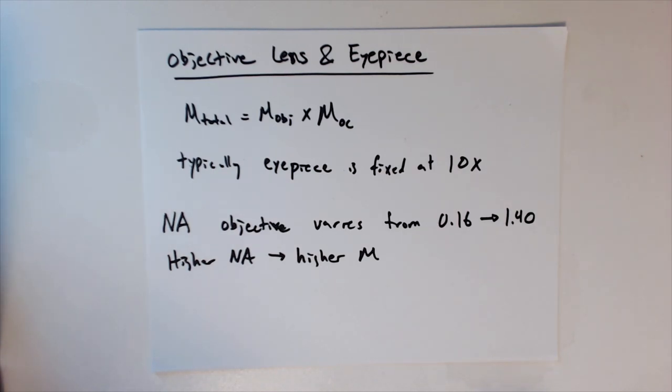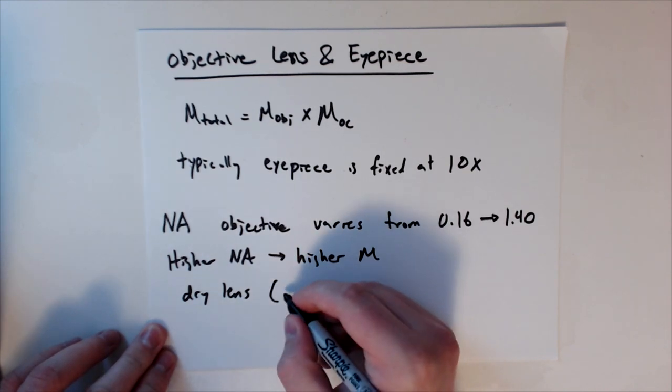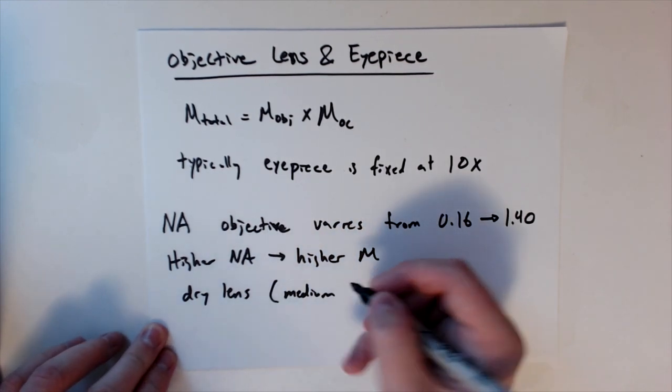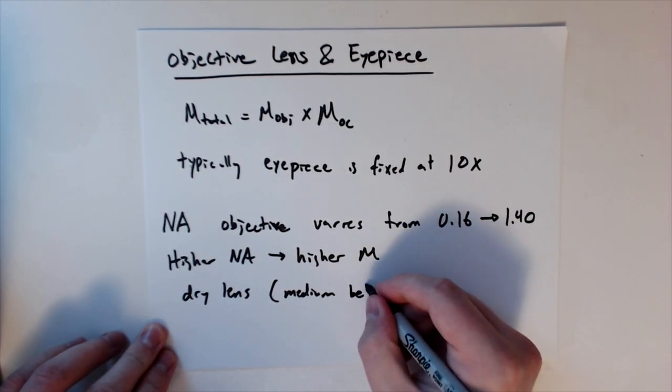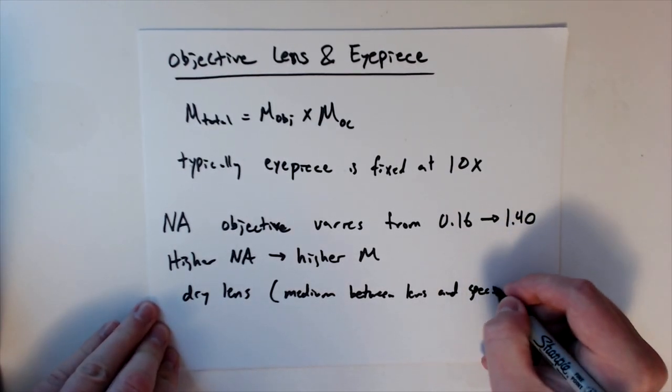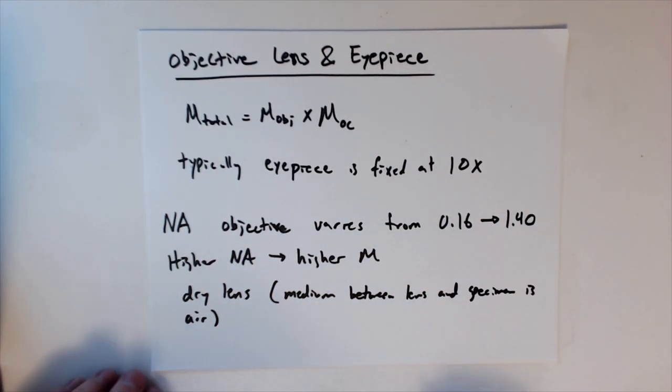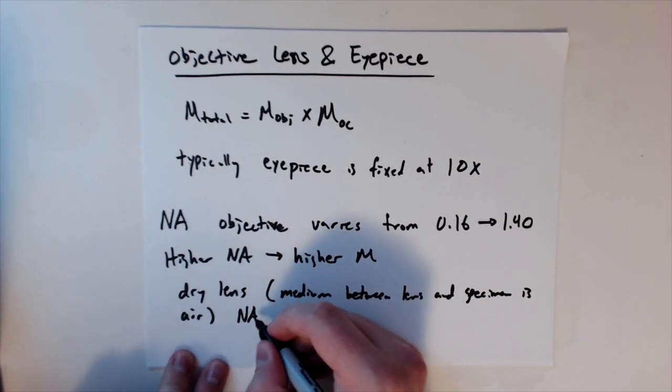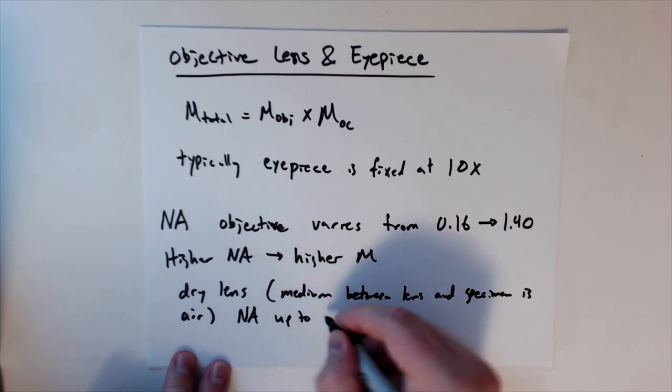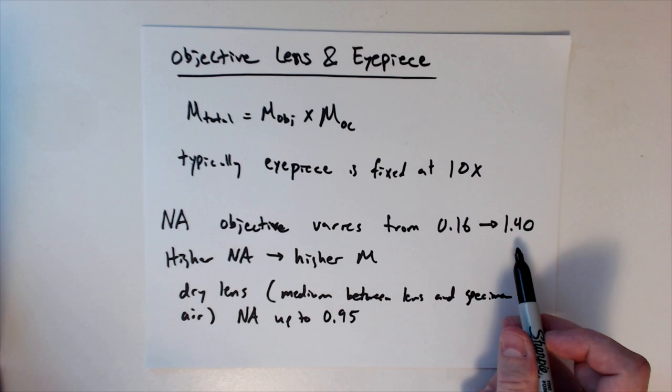Also, we have two types of lenses. We have what's called a dry lens. And this is where we just have medium, the medium, so the fluid between the lens and specimen. And this is air. All right, so it's dry because it's air. And so that can have a numerical aperture of up to 0.95. So you can see that this doesn't quite reach one, yet I said that it can vary up to 1.4.